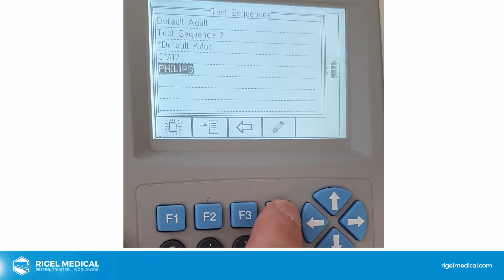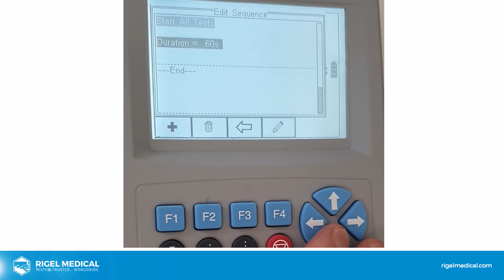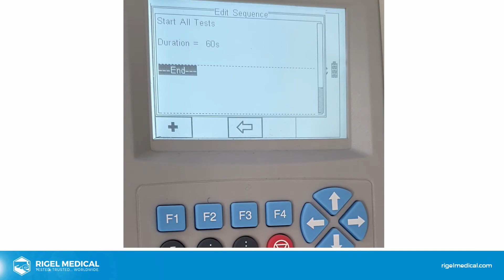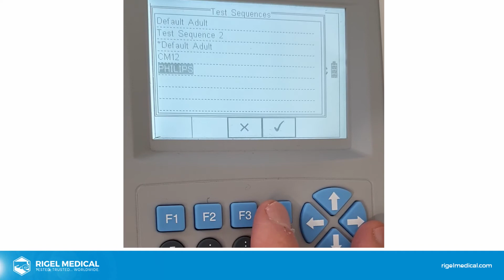One more thing I'll just add on there when you edit the tests. We've got start all tests. If you want to add extra values for patient simulation, you might want to go for a sequence of tests. You can add them here at the end and then select start all tests again, and that will give you the option to record all those values. It's important to note that with the Uni-Sim, the values cannot be recorded during the simulation, so you'll need to note down the values you get on screen on your monitor, unless of course your monitor is able to save those values. Then you can save them and input them later, but it doesn't come up during simulation, only at the end of the test.